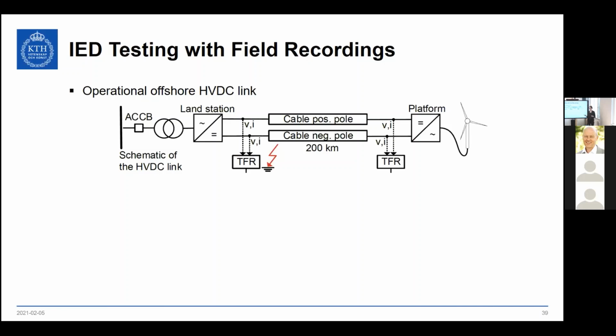We were very lucky in the project to get field recordings from a fault in an operational HVDC link. This is a very simplified diagram of that link: we have a land station, a platform with an offshore wind farm, and a fault happened on the negative pole close to the land station, in a cable joint.